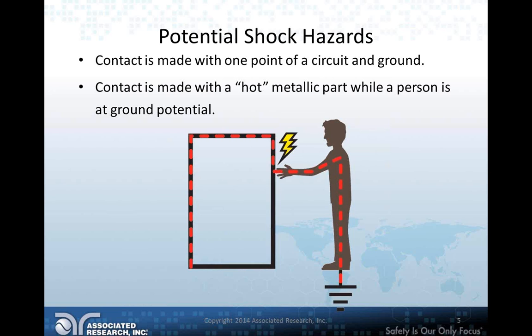It can also happen where contact is made with a hot metallic part while the person is at ground potential. You don't necessarily need to come in contact with something like a line conductor. Say you have a large metal chassis on a device, and internally one of the live energized conductors is frayed and is now contacting the chassis of whatever machine this might be. If you come into contact with that chassis and you look like a low resistance path for the current, it's going to go through you.